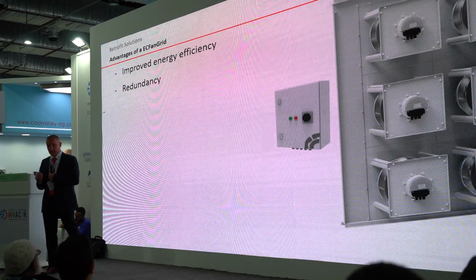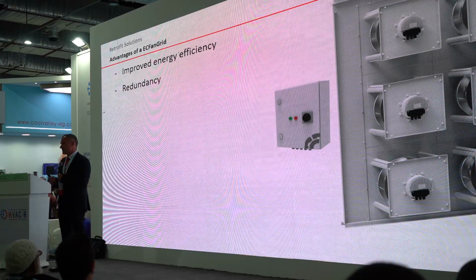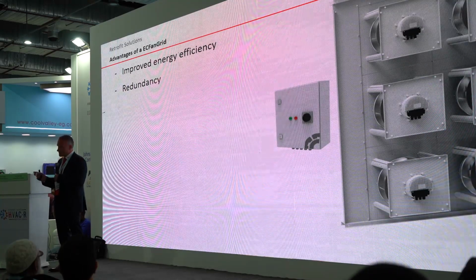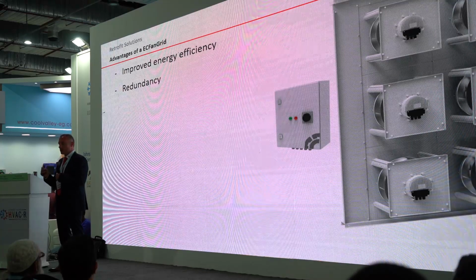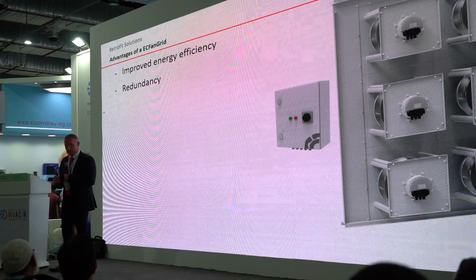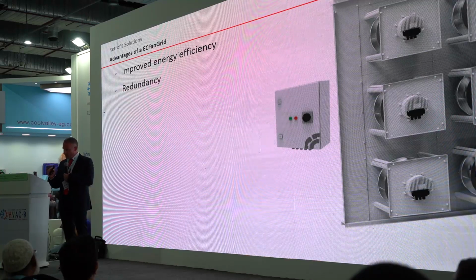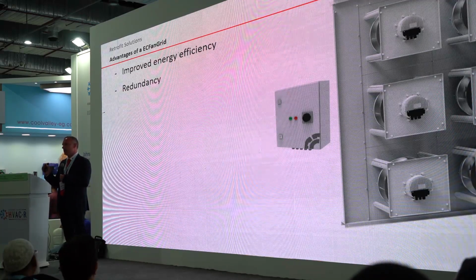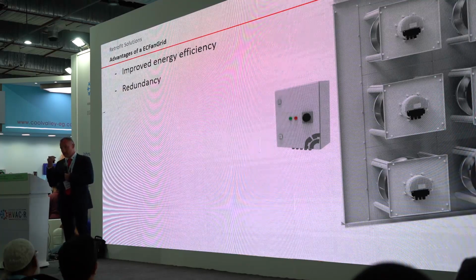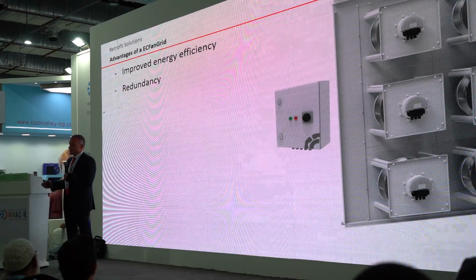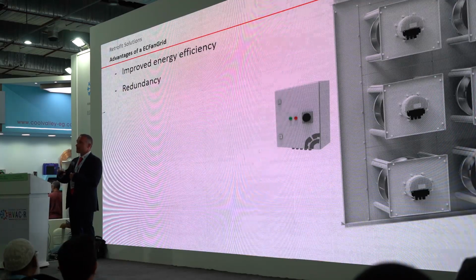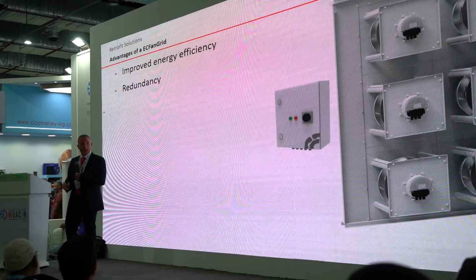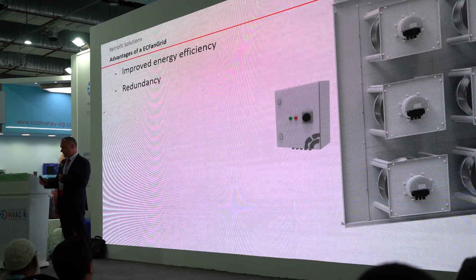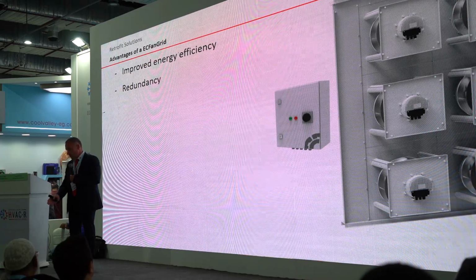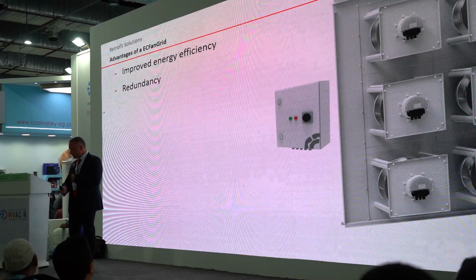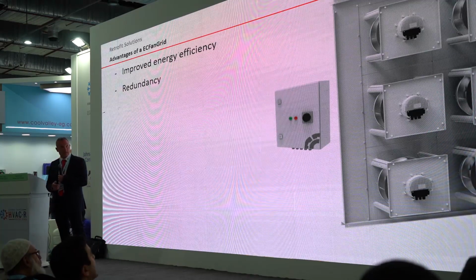And this is the point when we are in contact with the customer, and the customer says yes, he needs redundancy, 100%, the unit should go to 0 downtime. Then we can set the operating point with a certain level of reserve. In case one fan goes down, the other fans can go up in speed and cover this fan. We can also deliver sheet metal plates to cover the hole, so that the air is not going in a circle in case of a failure.